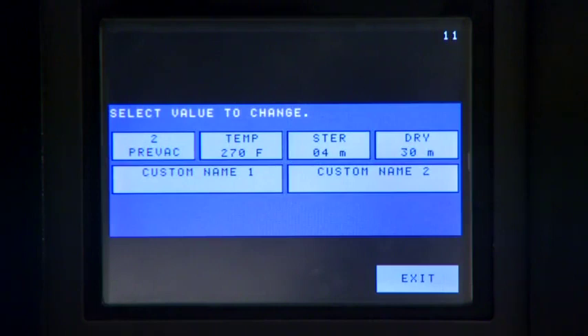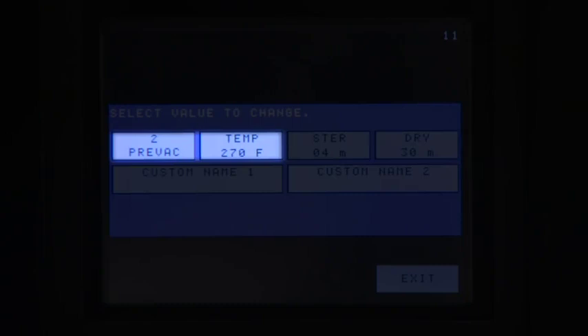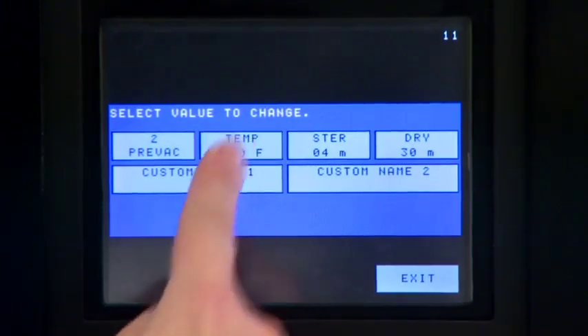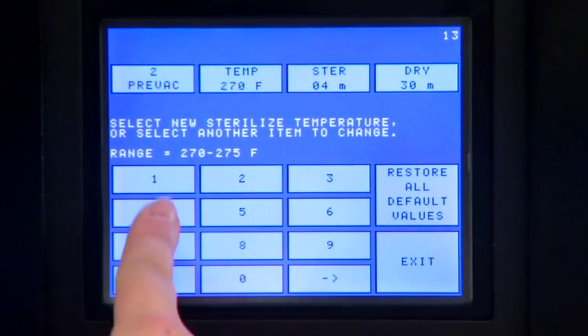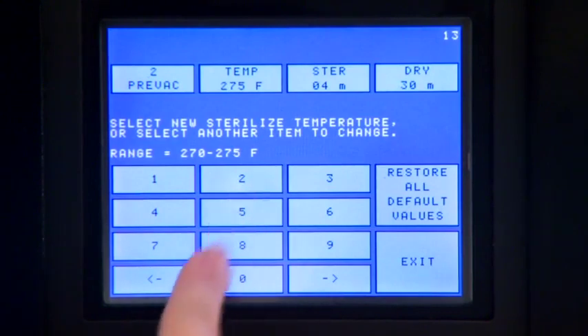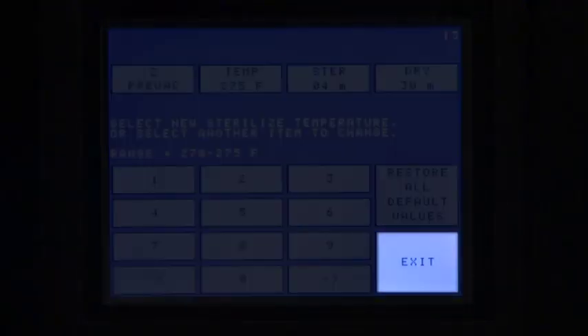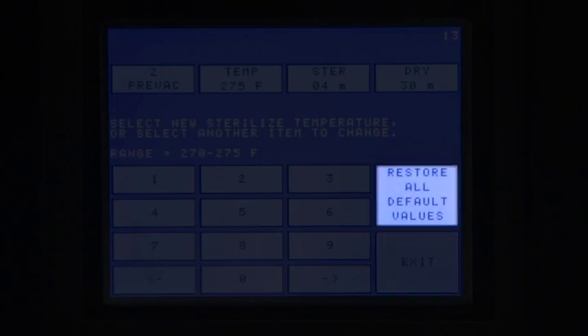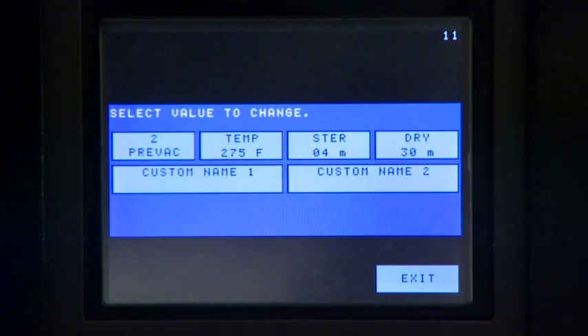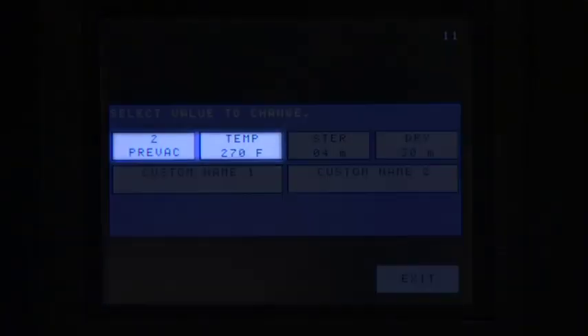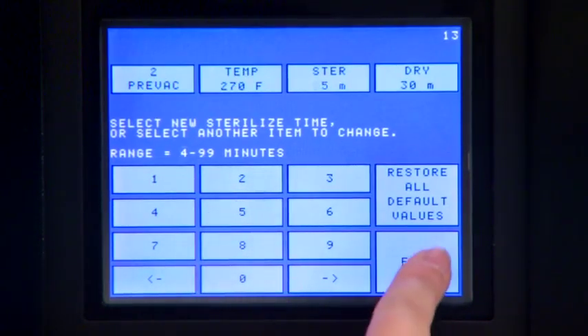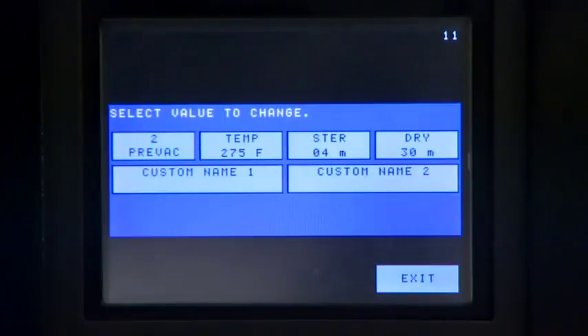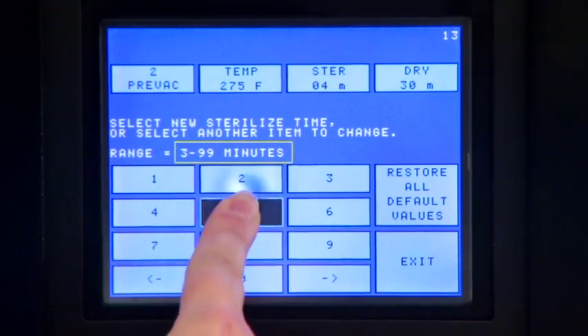Choose the cycle type. Then choose the cycle parameter you want to change. For example, to change the sterilizer temperature value for a Prevac cycle, enter the desired temperature into the keypad, ranging from 270 to 275 degrees Fahrenheit. If you make a mistake, use the backspace button on the keypad to erase what you entered. Press the Exit button to accept the new value, or press the Restore All Default Values button to keep the factory set cycle value and return to the Change Cycle screen. To adjust the sterilize time for a 270 degree Fahrenheit Prevac or SFPP cycle, enter the new value, ranging from 4 minutes to 99 minutes. A 275 degree Fahrenheit Prevac or SFPP is adjustable from 3 minutes to 99 minutes.